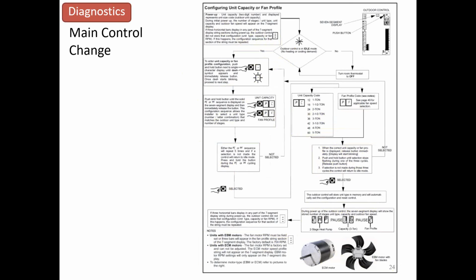Okay, we also have capacity of this unit. So we talked about that. So here on the right hand side, I'm just going to kind of highlight what you might see. You see here that it's got a 12 for a 1 ton, 18 for a 1.5 tons, all the way down to a 5 ton on unit capacity code. And once you get in the system, it's going to let you do multiple things. You'll be able to set the outdoor fan, what it needs to be. It will accept up and down on that fan, so you can actually slow the fan down in certain applications.